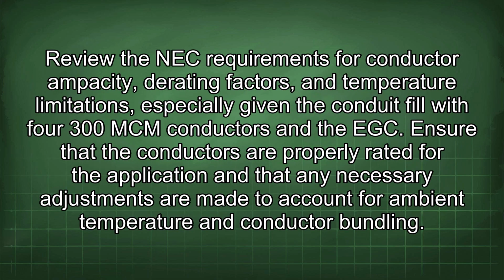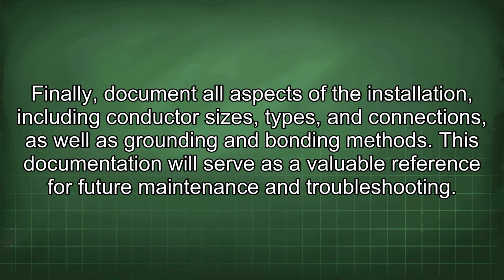Review the NEC requirements for conductor ampacity, derating factors, and temperature limitations, especially given the conduit fill with 4 300 MCM conductors and the EGC. Ensure that the conductors are properly rated for the application and that any necessary adjustments are made to account for ambient temperature and conductor bundling. Finally, document all aspects of the installation, including conductor sizes, types, and connections, as well as grounding and bonding methods. This documentation will serve as a valuable reference for future maintenance and troubleshooting.